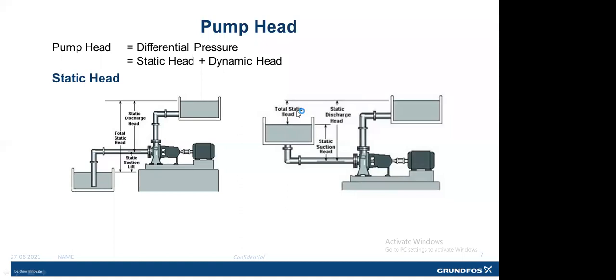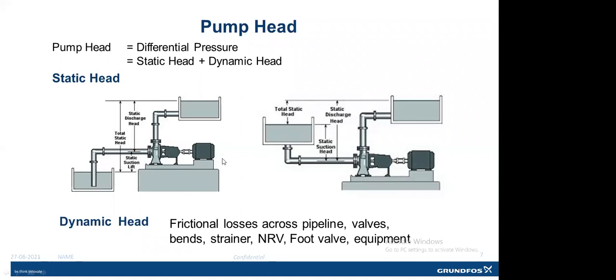And in that case, only dynamic head needs to be taken into account, which consists of frictional losses across the pipeline as well as valves, bends, strainer, NRV, foot valve, and equipment. The pressure loss across the equipment is the most important factor to be considered while designing the pump. So while selecting the pump, we need to consider both static head as well as dynamic head.